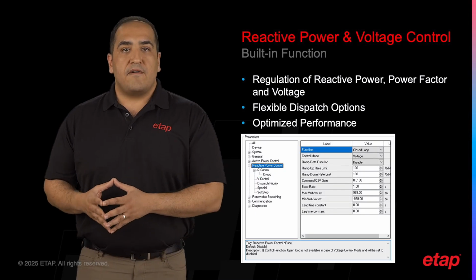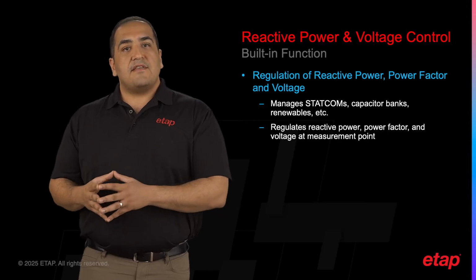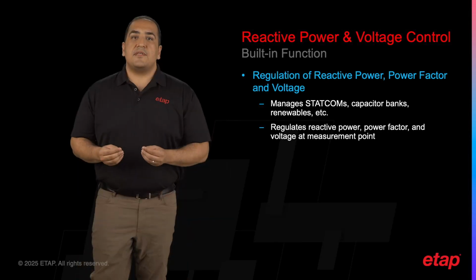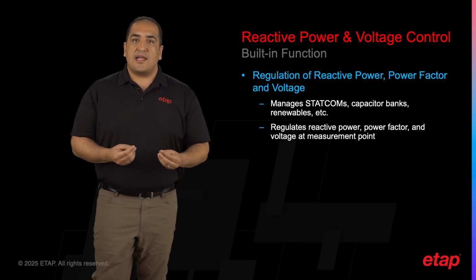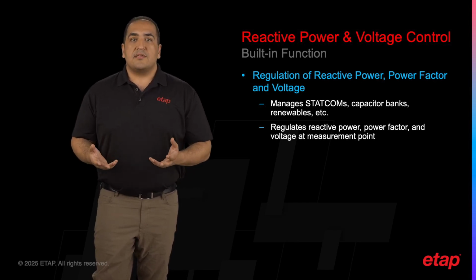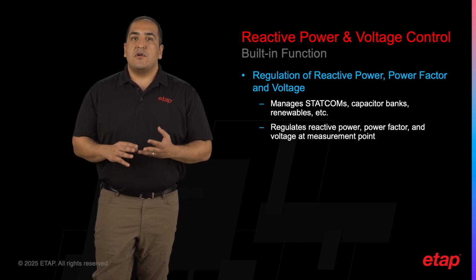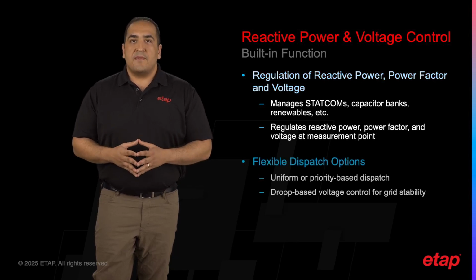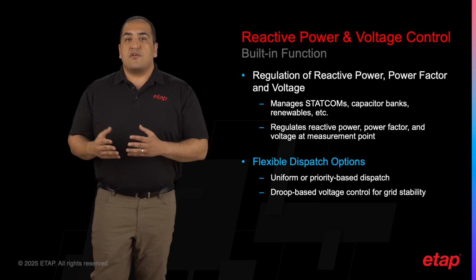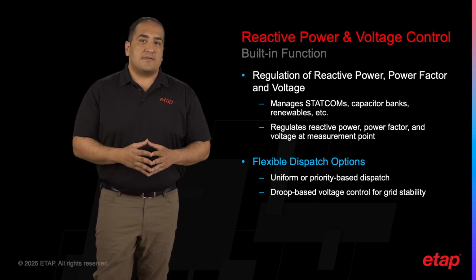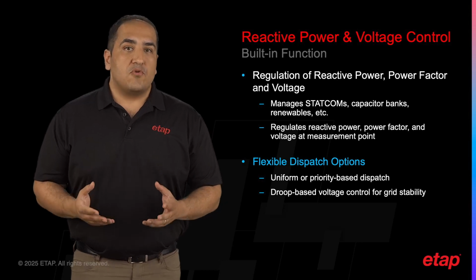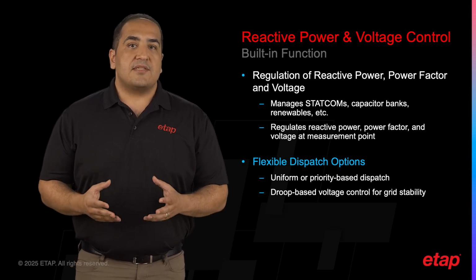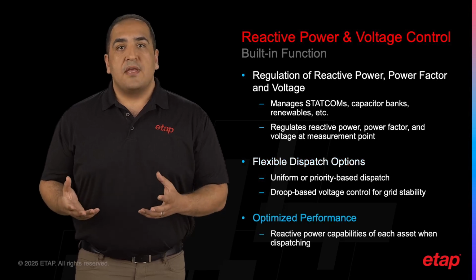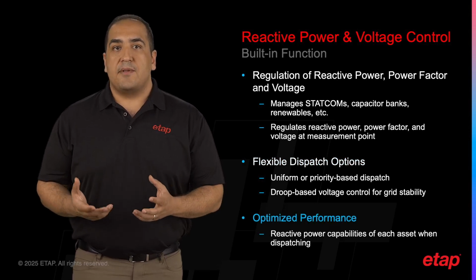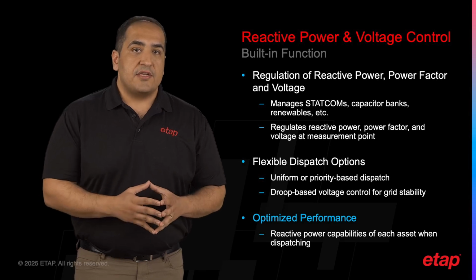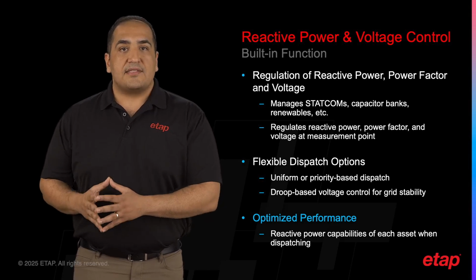Next, we have reactive power and voltage control. In the reactive power and voltage control loop, EPPC manages various resources such as STATCOMs, capacitor banks, and renewables to regulate reactive power, power factor, and voltage at the point of measurement. This regulation is achieved through either uniform dispatch or priority-based dispatch. The solution also supports droop-based voltage control, which helps stabilize the grid voltage. Importantly, EPPC considers the reactive power capabilities of each asset during dispatch, ensuring optimal performance and stability.